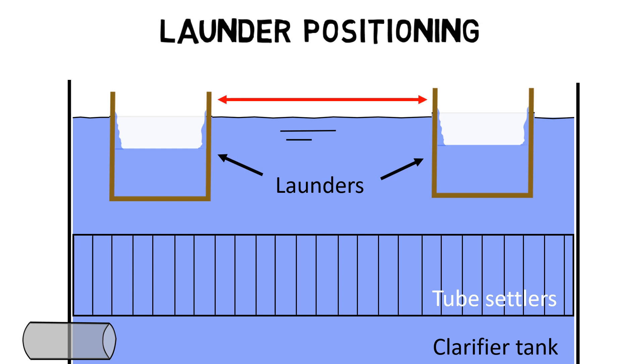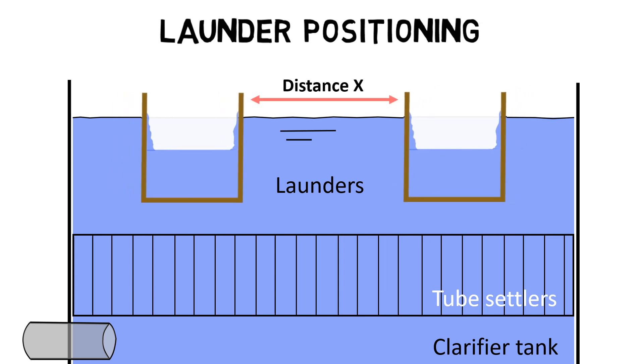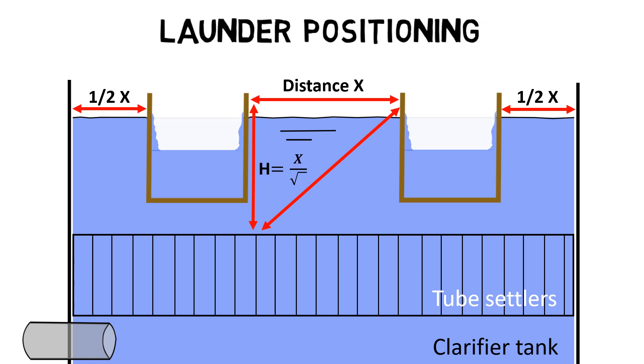As a rule of thumb, the distance between effluent launder to effluent launder should be x. The distance between basin wall and effluent launder should be half x. And the distance between the top of the tube settler and the top of the effluent launder should approximately equal the distance between two launders divided by the square root of 3, divided by 2.